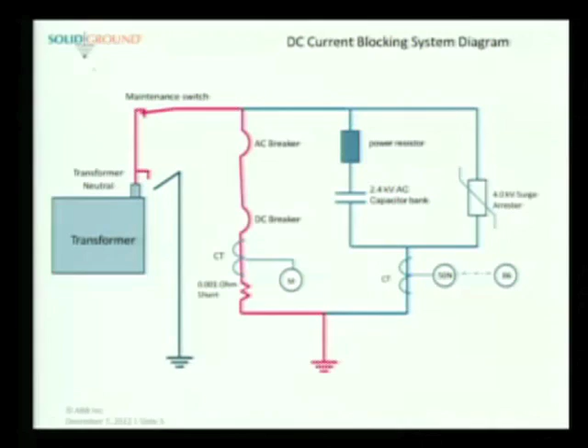When the switches open, then we're grounding the system through a 1 ohm resistor and a 1 ohm impedance capacitor bank. Now this is very low impedance that we're putting in, so it will not cause any resetting of the relays in the system. And I should point out that we believe 99% of the time we will be grounding the transformer just like it's always grounded, through a metallic path to ground. What we're doing is sensing and then protecting. And so when we sense the presence of GIC or harmonics, we then ground it through the capacitor.